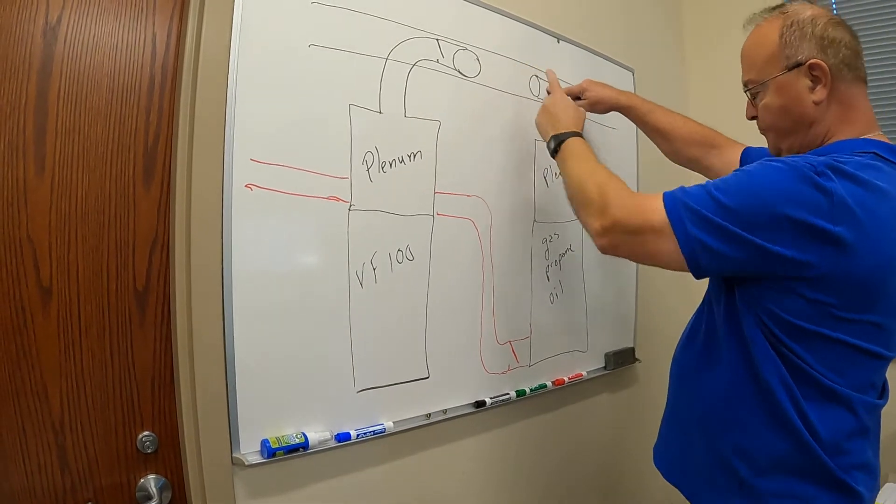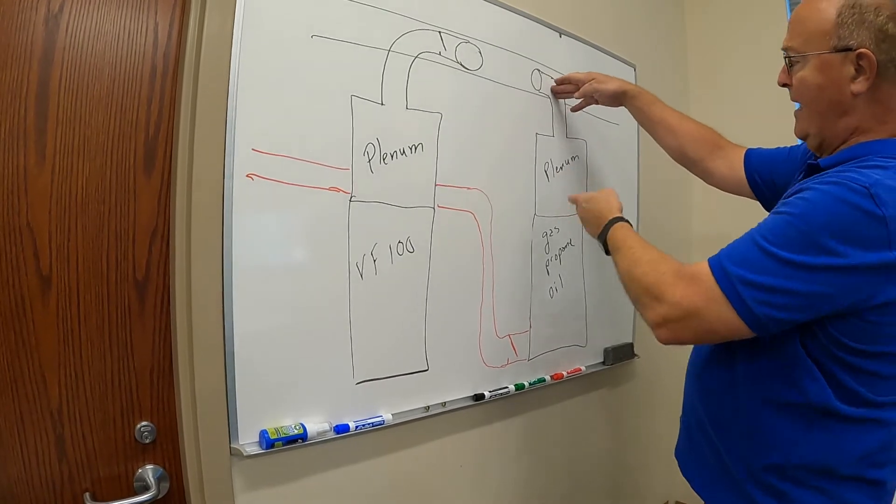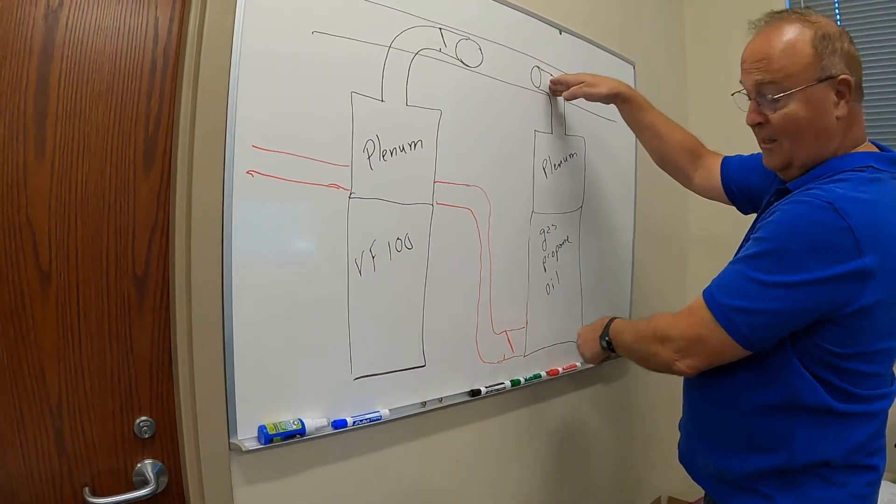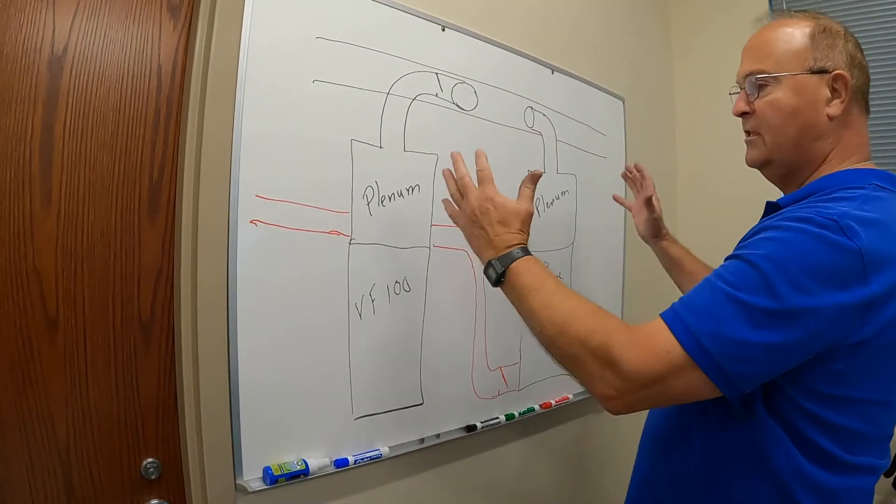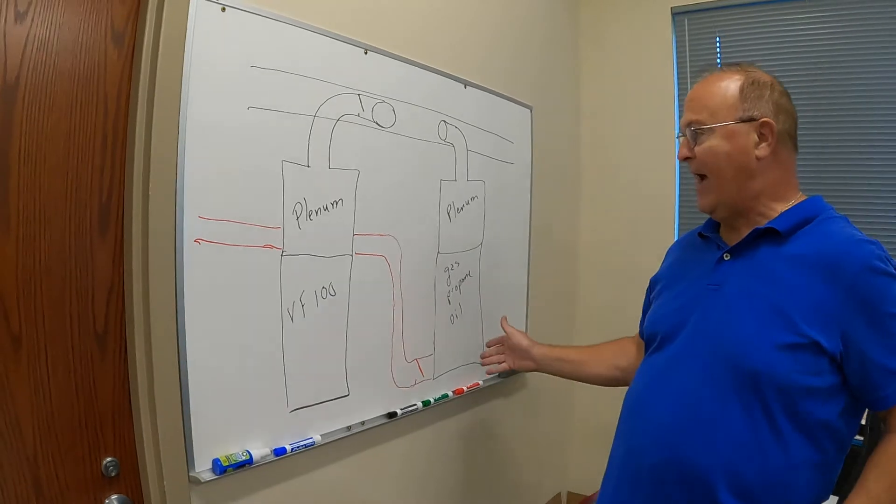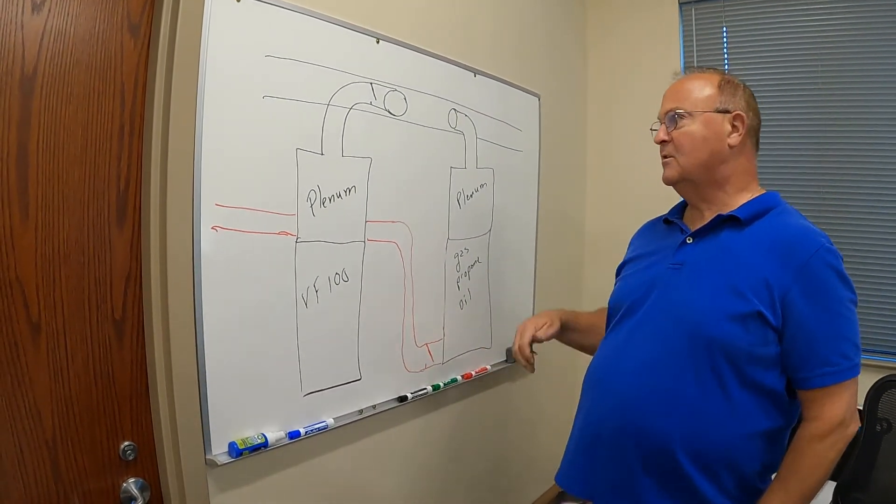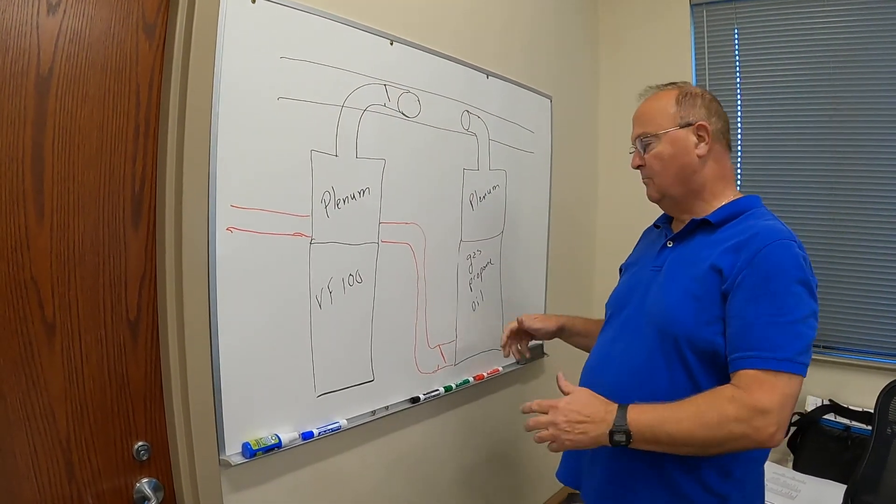But now if you have a backdraft flap on the cold air return, it can't push air back down here because that flap's going to lock shut and it won't let you push hot air back down through there. So that's the two setups for setting up your backdraft flaps. You can put them in the cold air returns, probably best in the warm air section of the furnace, but either way works fine.